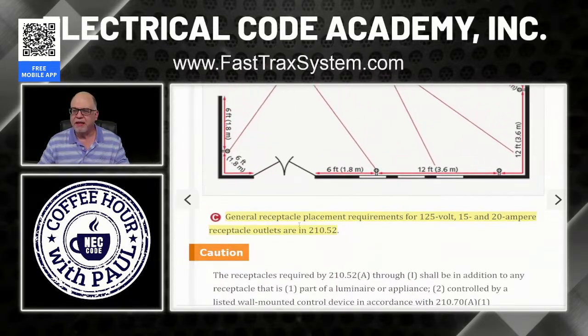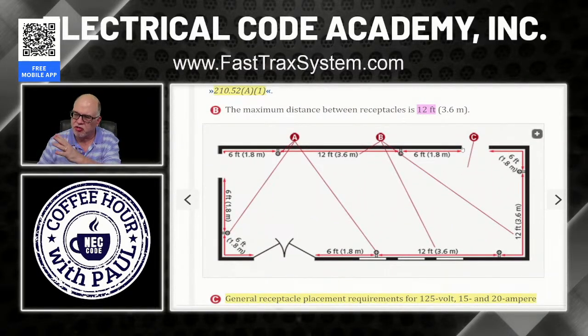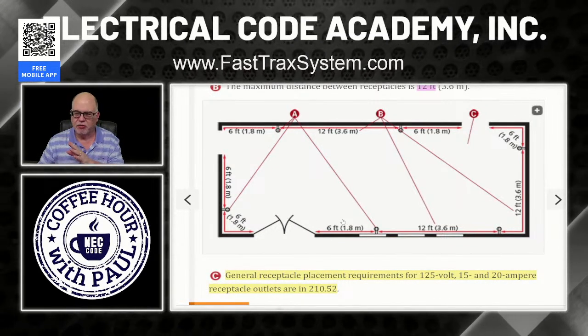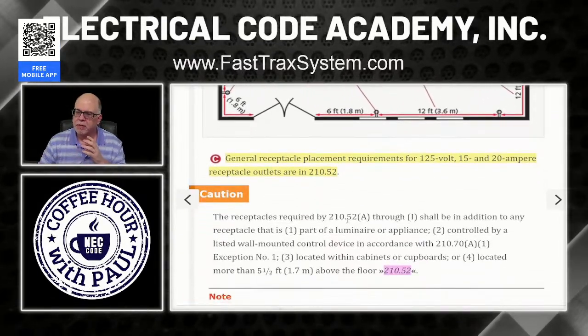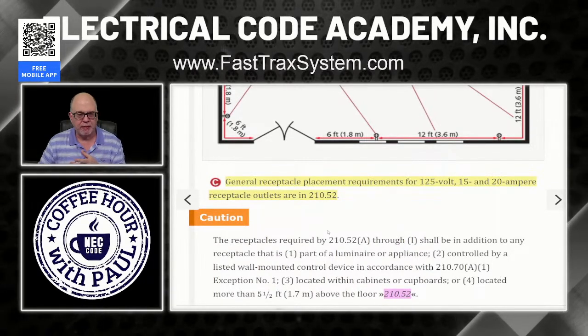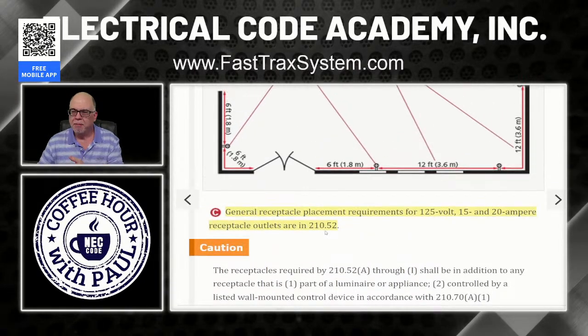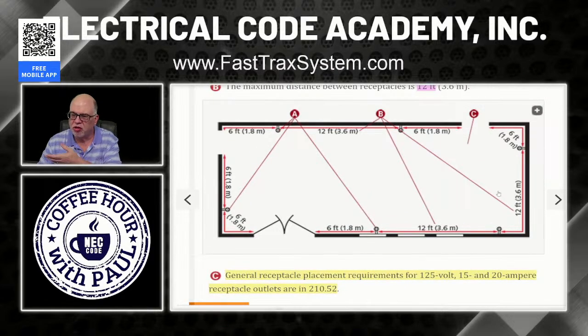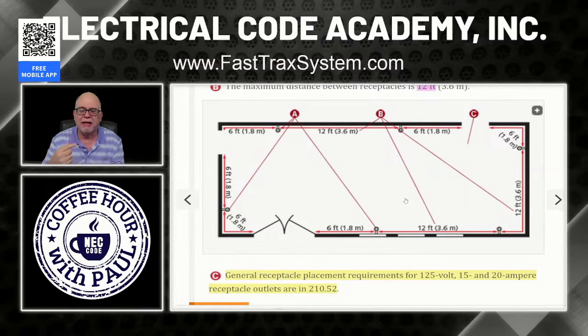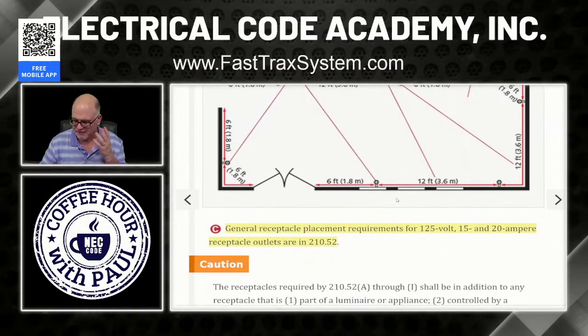So these are the general purpose receptacles, and you have to have them based on that 6 foot, 12 foot example that we gave you, right? But you could have a luminaire or an appliance with a built-in receptacle. Well, that's okay, but it can't take the place of these general receptacle placements. It's just an extra one. So you could have it in an appliance in the room, but it can't qualify as the ones that are required by 210.52. Can't meet that.